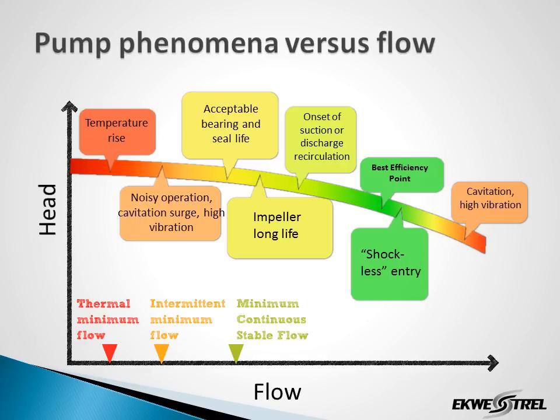The problem with an oversized pump is it will operate at reduced flows where various undesirable phenomena may occur. For example, here we have the best efficiency point area, and as we reduce flow, we get into suction recirculation, discharge recirculation, cavitation issues affecting the impeller life, increased vibration affecting the bearing and seal life, and as we reduce even further, instability and temperature rise issues can happen.